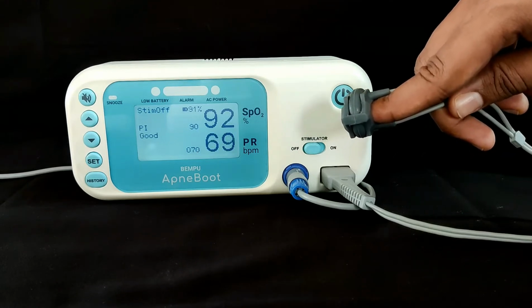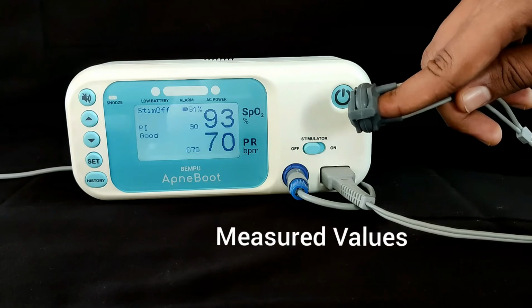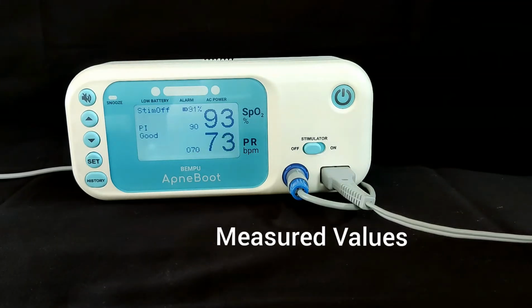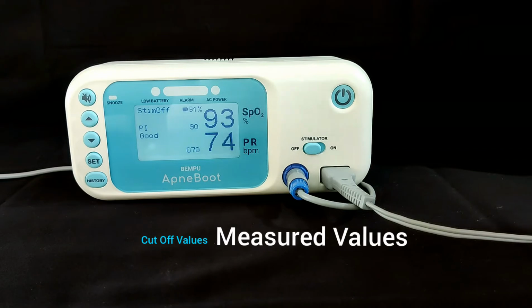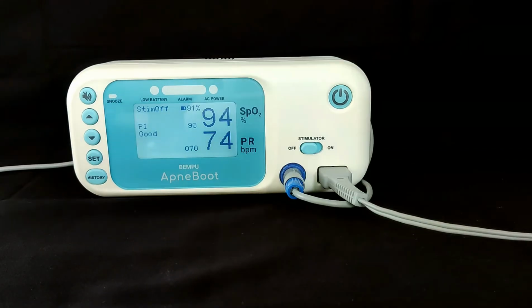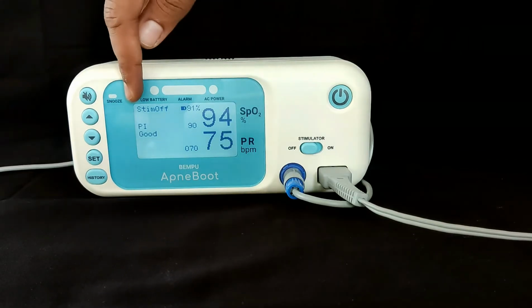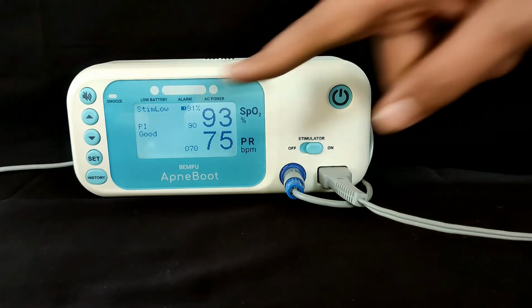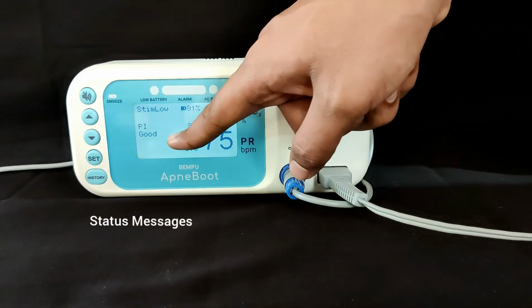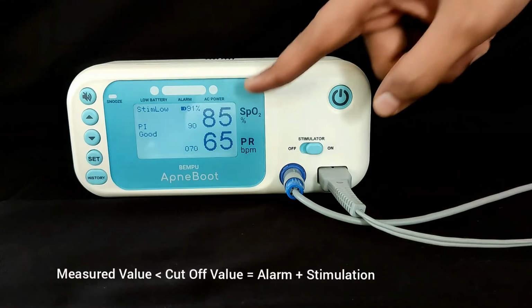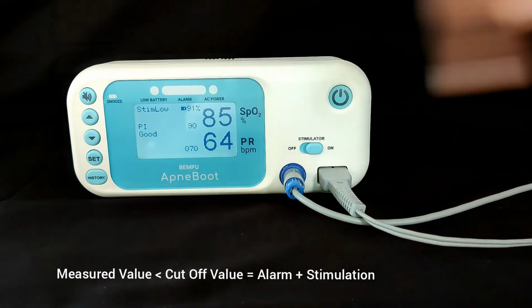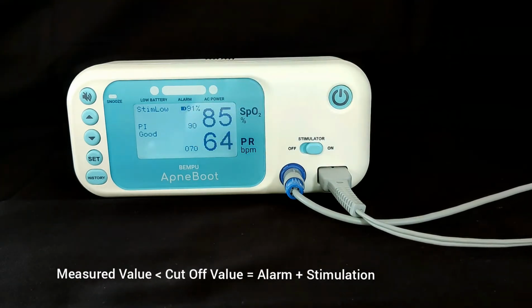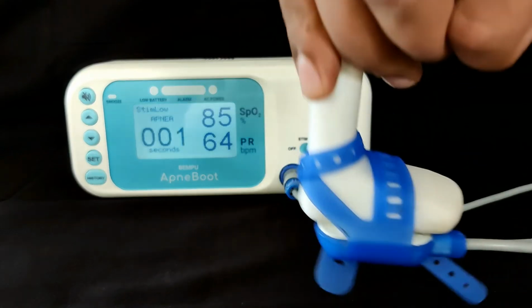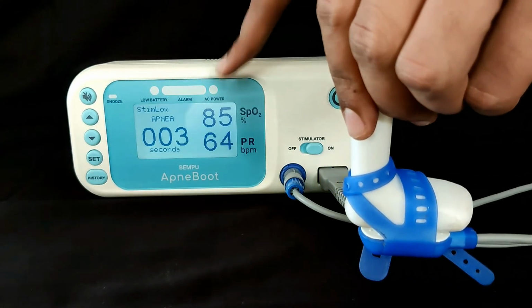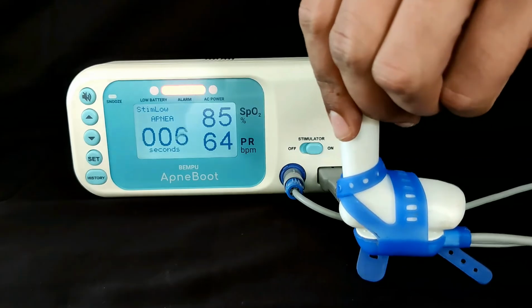The screen will display the measured values of SpO2 and pulse rate in these big size letters and the cutoff values in the adjacent smaller size letters. On the top corner of the screen, it displays the stimulation intensity. It also shows the perfusion index, the device messages, or apnea duration in the event of an apnea. When the measured values go below the set cutoff values, it identifies as an apnea and gives a vibratory stimulus to the foot sole like this. It also displays the apnea duration on the screen.